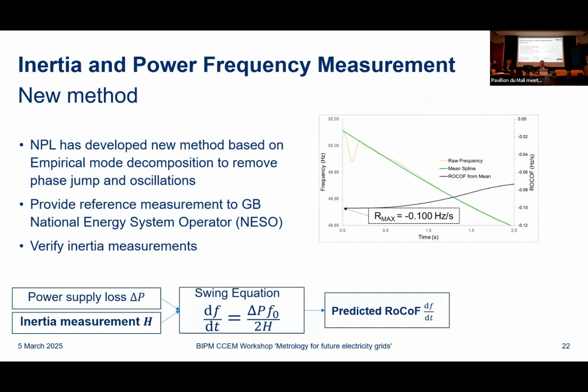And we've been providing that as a reference measurement to the transmission system operator in the UK. And they can use that in order to make a comparison with the frequency response that's predicted when they have an inertia measurement, maybe an inertia value that they've calculated, or in this case, also an inertia measurement that comes from a new commercial system. So in terms of validating new systems that are coming onto the market, I think metrologists have also a large role to play here.